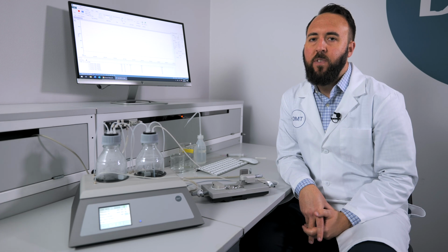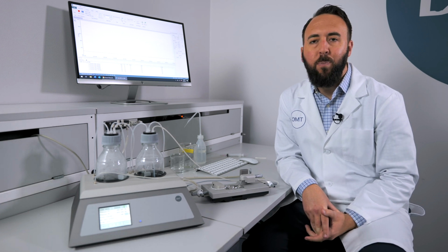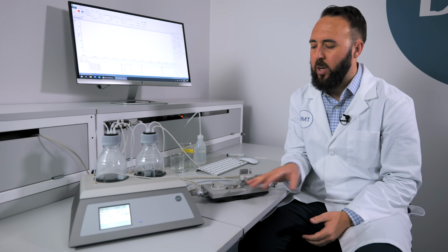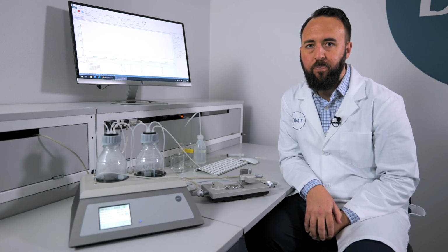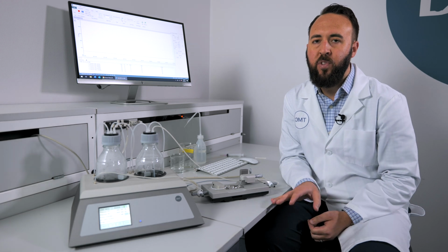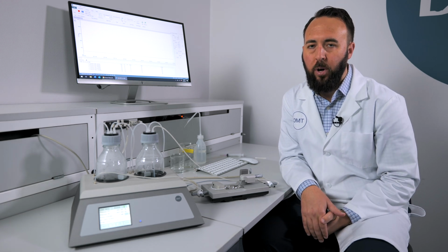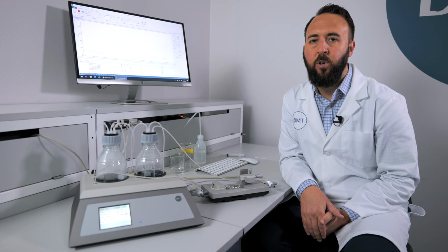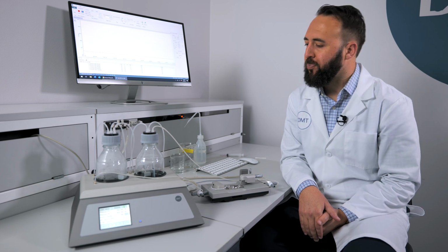For a deeper clean of the system, we recommend using 8% acetic acid. This is not necessary after every experiment. Typically, if you see salt deposits start to accumulate in the chamber, that's when it's a good time to do a deeper clean. But make sure if you do use acetic acid that you do a thorough water wash after the exposure to the acetic acid.